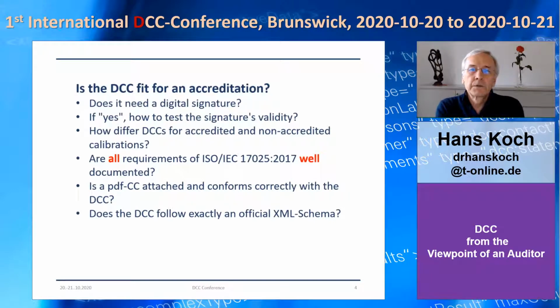So what are the points to touch? Is the DCC fitting for an accreditation? There are several aspects. Does it need a digital signature? If yes, how to test the signature's validity? How do DCCs differ for accredited and non-accredited calibrations? In Germany we would call the latter Werkskalibrierung. Are requirements well documented? Is the conventional certificate attached and does it conform correctly with the DCC? And does the DCC follow exactly the official XML schema?